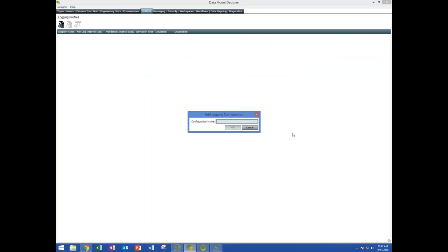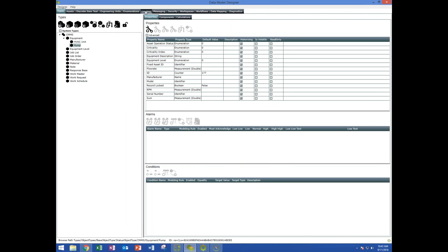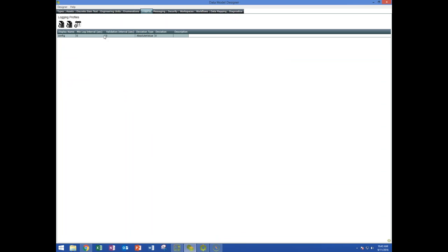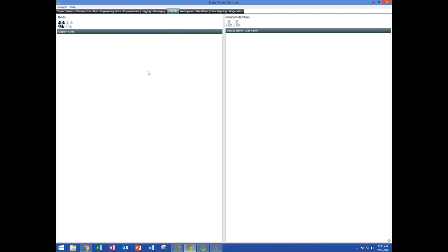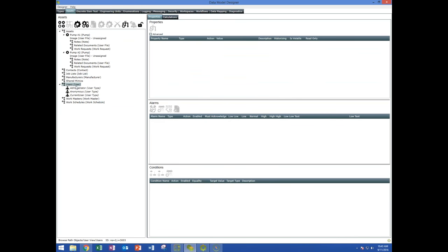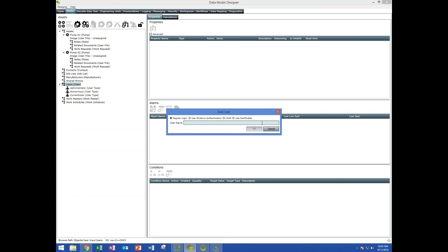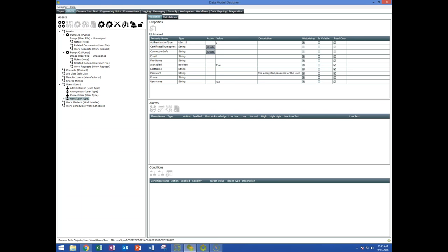Logging: you can define a more complex logging configuration. By default, just hit the historizing checkbox and you get logging. But if you want more control — maybe you don't want your database to fill up so fast and only want to log values every five minutes instead of on every value change — you can do that. Messaging is for setting up email notifications with alarms. Security: there are users and roles. Users are created in the assets tab. Authentication can be regular username and password, Windows authentication, LDAP, or X.509 certificates.